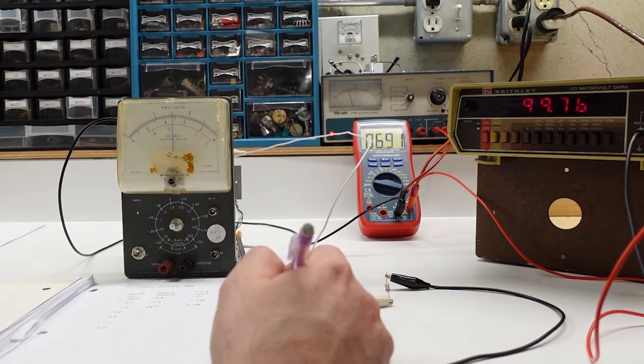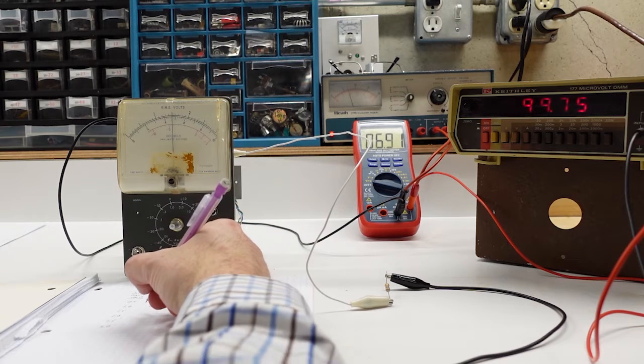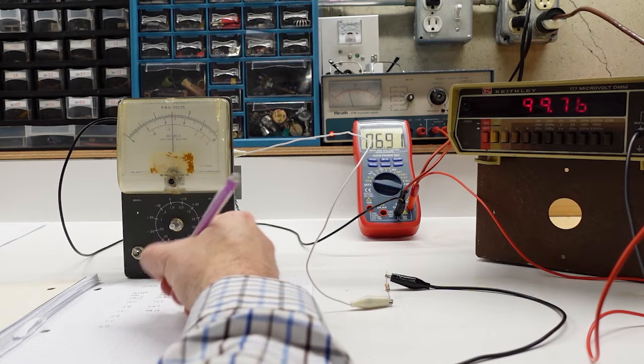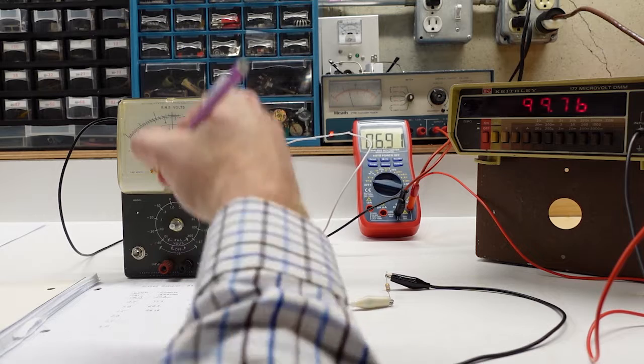The best way to do this test is to use an adjustable power supply with a current limiting resistor in series with the meter. I use 68K in this case, and adjust the voltage to make the needle align with the scale every half a volt, and then record the Keithley reading.